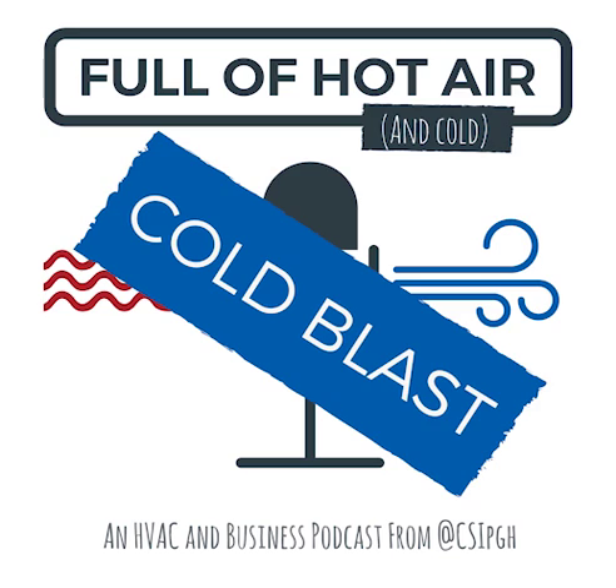So get your pen or pencil and paper out for this and start scribbling. The formula is, first, look at the data plate of the furnace. Our example is going to be a 60,000 BTU furnace, and let's say it's 96% efficient. The first formula is to take that 60,000 BTUs times 0.96, because we want to know the output of that furnace. The output of that furnace would be 57,600 BTUs.